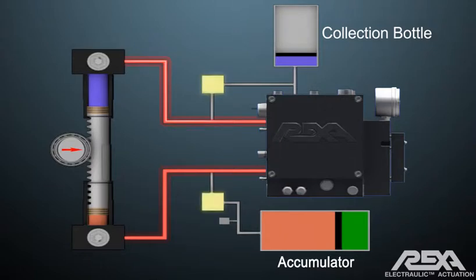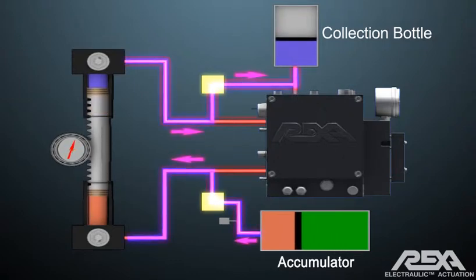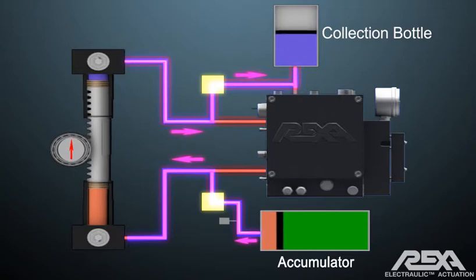On a trip condition, the solenoid valves will open. The nitrogen-charged accumulator will push oil into the connected hydraulic cylinder, while the collection bottle will provide a volume for the other side of the hydraulic cylinder to empty into. The connected valve or device will be positioned to the design trip position.